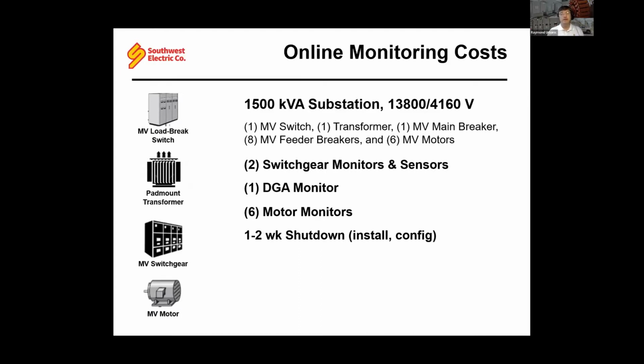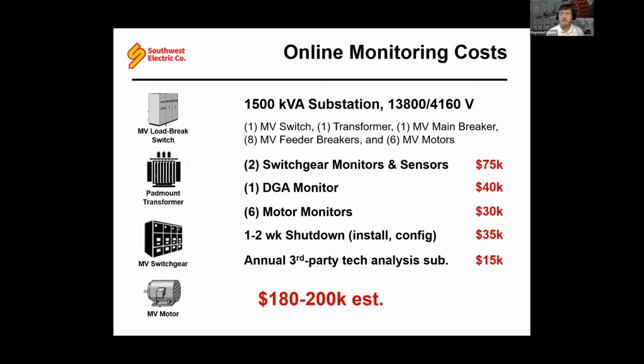You're going to need, I mean, 1 to 2 weeks is probably pretty optimistic, but you're going to need a significant shutdown to not just install these sensors and all the wiring, but also the configuration of all the settings you're going to need in your devices in order to properly monitor this. And then, unless you've got staff already at your facility, you're probably going to need some kind of third-party analysis assistance in order to do all this. And if you start adding up these budgetary costs, you come up to a pretty good investment just for one substation.